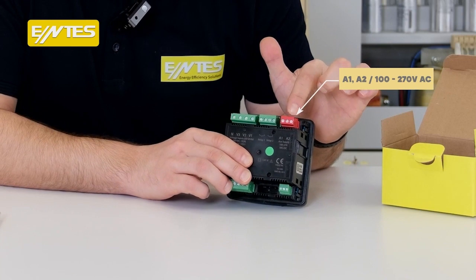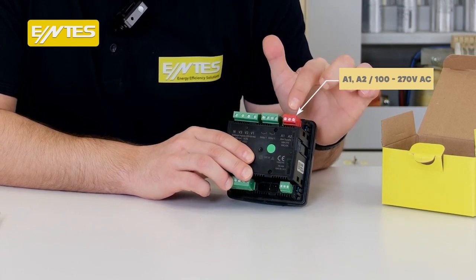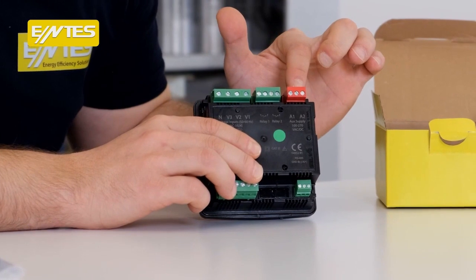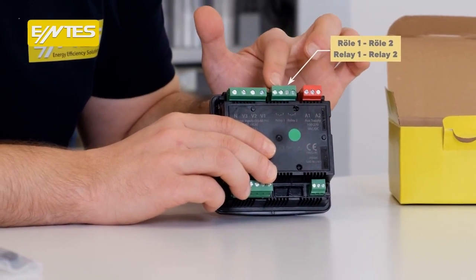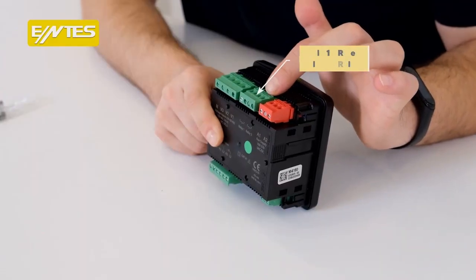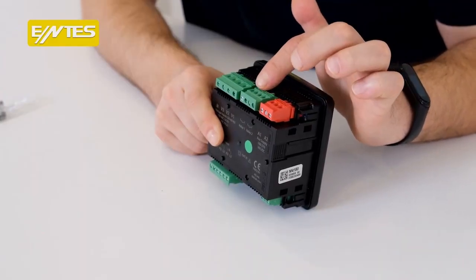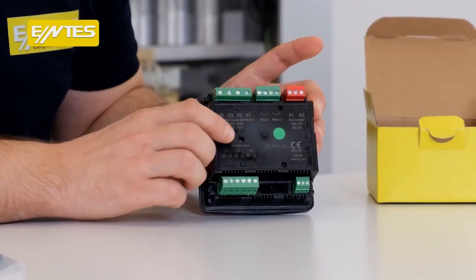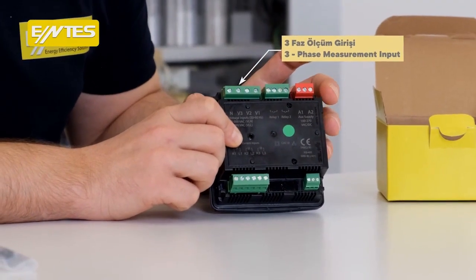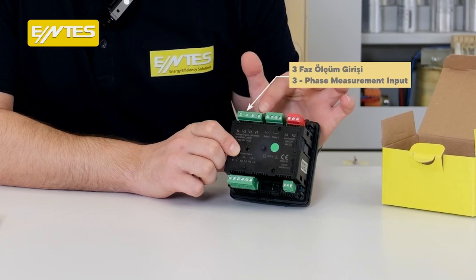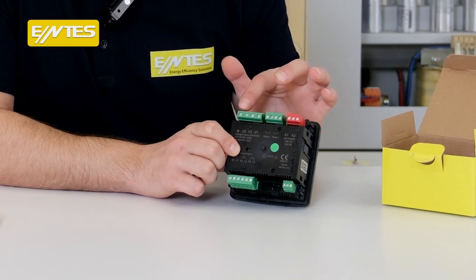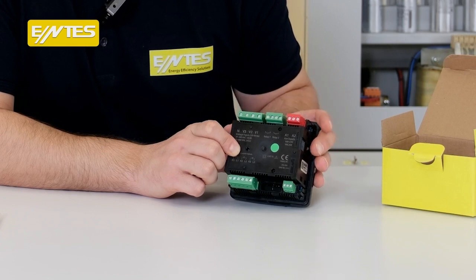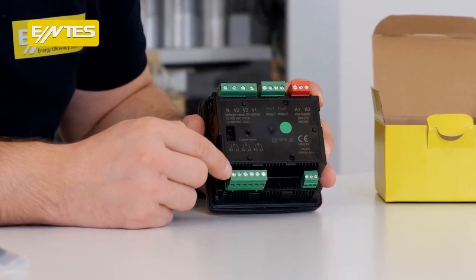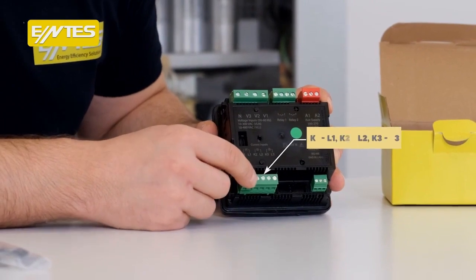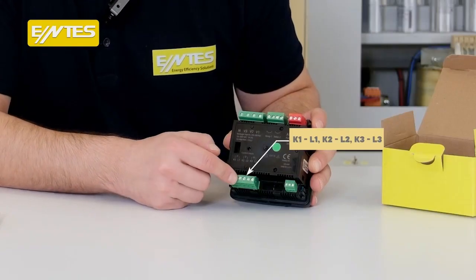Here, red clamp A1, A2 should be applied with 100-270 volt AC voltage. Since the product has a contact output feature, there are relay 1 and relay 2. When we assign an alarm parameter here, we can get a contact output. There are 3 phase measurement inputs on the right side of the device. This is suitable for 10-300 volt AC phase-neutral, 10-480 volt phase-to-phase connection. Connect like this: K1L1, K2L2, K3L3 terminals from our transformers on the lower side again for current measurement.